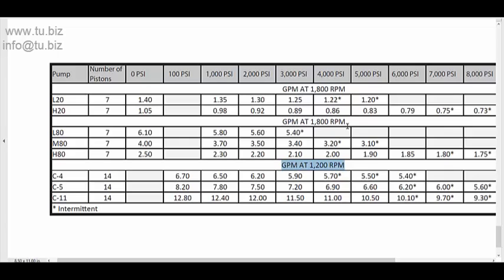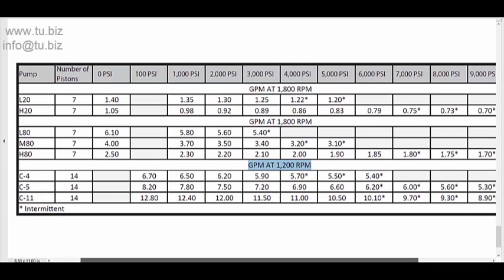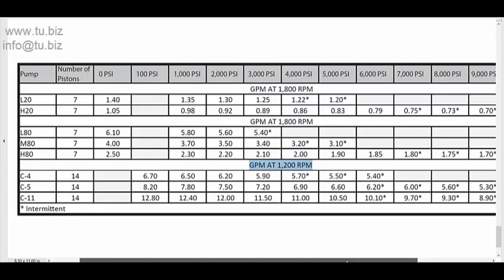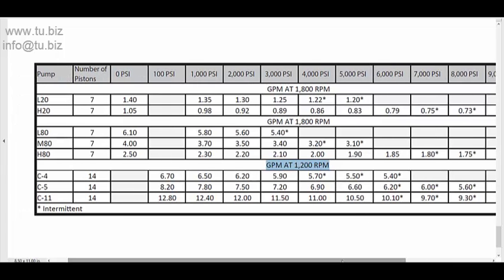So the best way to pick a pump is by coming to this chart and you can see the maximum continuous pressure and the GPM that is going to give you at that pressure. Also, you would notice if the pressure goes down, the GPM goes higher up. So that's another thing you can look at, the different flow they will give you at different pressure ratings.